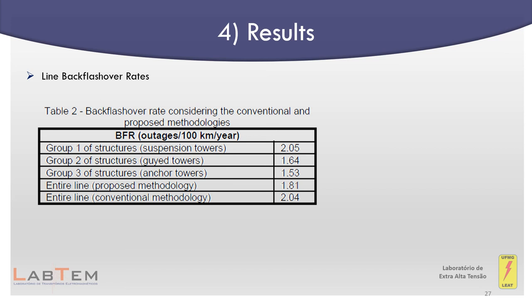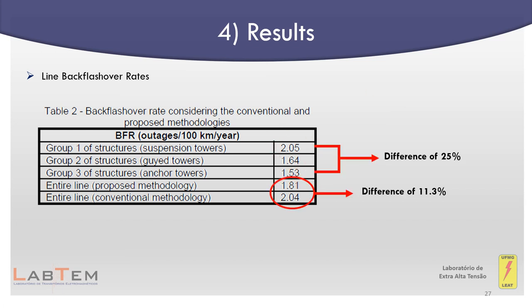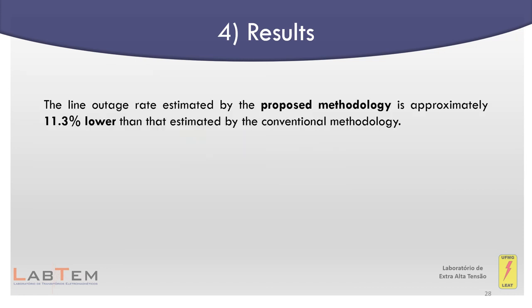The line backflash-over rates were calculated using the conventional and proposed methodologies. Table 2 summarizes the obtained results assuming NG equals 5 flashes per square kilometer per year. The group of anchor towers has the lowest backflash-over rate, followed by the group of guyed towers, and finally the group of suspension towers presents the highest rate. The line outage rate estimated by the proposed methodology is approximately 11.3% lower than that estimated by the conventional methodology, stemming from the better performance of the guyed and anchor tower groups compared to the dominant suspension tower group assumed in the conventional approach.